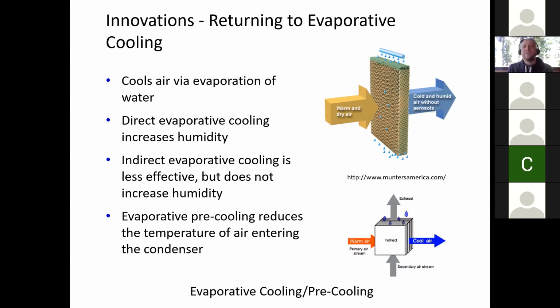One of our thermodynamic rules says we can't add or subtract energy from an airstream. All the air around us has some portion of that energy as temperature - the sensible heat you can feel, hot or cold - and a portion as moisture energy. For the total energy, or total enthalpy, to stay the same, if we add or subtract moisture, it changes the air temperature because the total amount of energy has to stay constant.